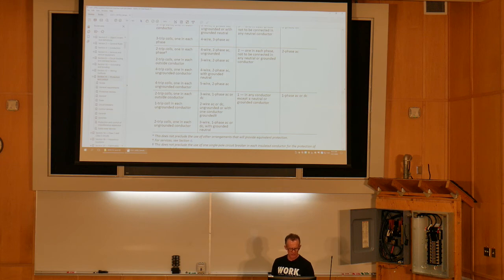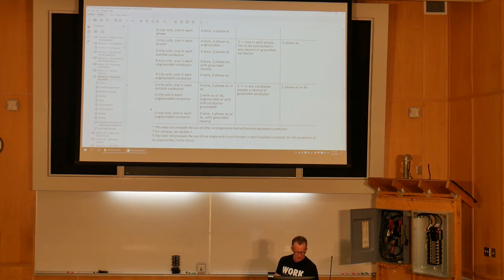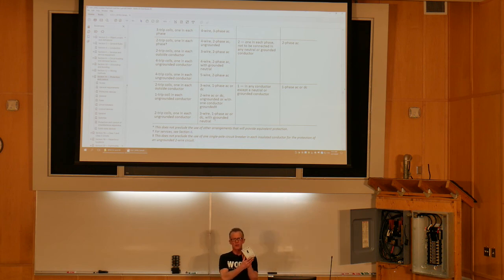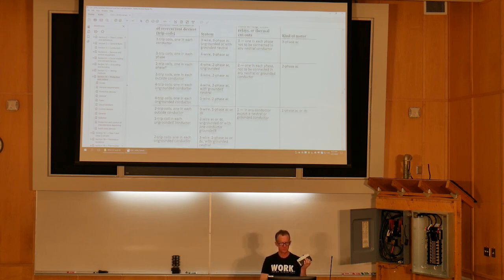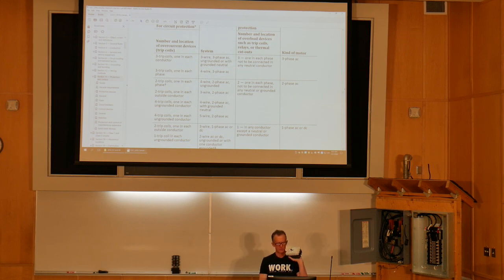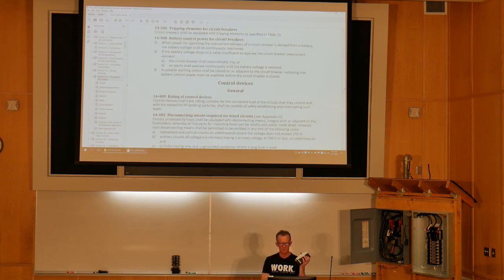2 trip coils, 1 in each outside conductor, 3-wire, single-phase AC or DC. 1 trip coil in each ungrounded conductor, 2-wire AC or DC with 1 conductor grounded. Then 2 trip coils, 1 in each ungrounded conductor, which corresponds to 3-wire, single-phase AC or DC with grounded neutral. So this is a 3-pole circuit breaker used on a 3-phase system. I have 1 handle that opens all conductors. So this would comply with this part right up here, 3 trip coils, 1 in each conductor, 3-wire, 3-phase, and it would also comply with this rule.